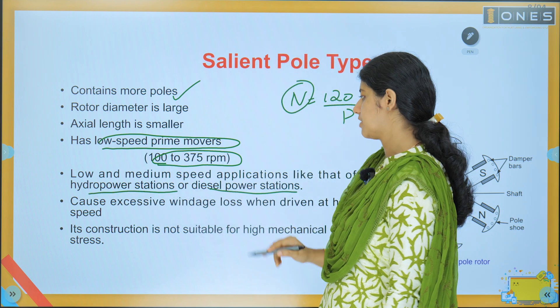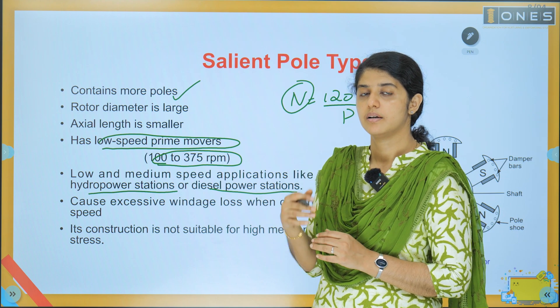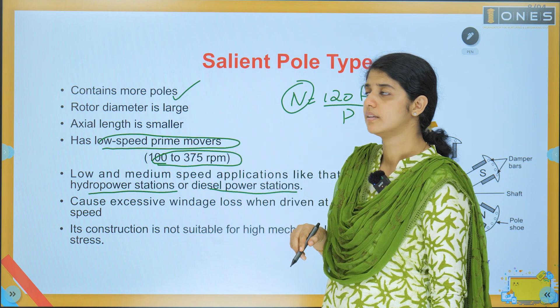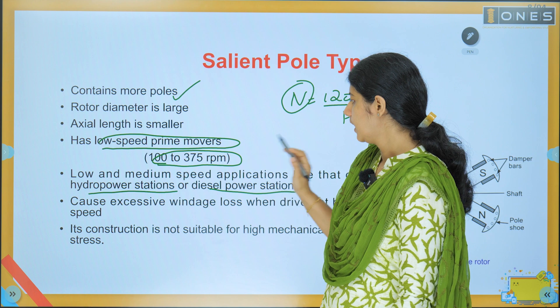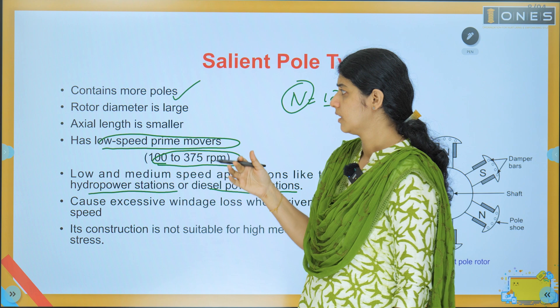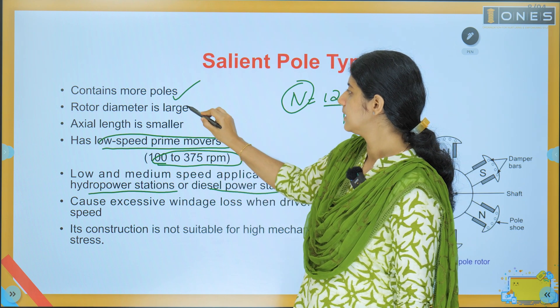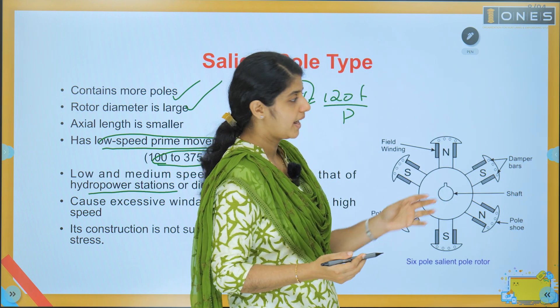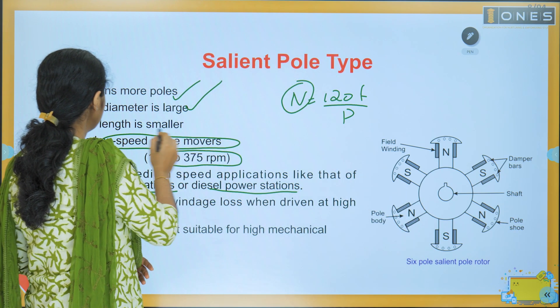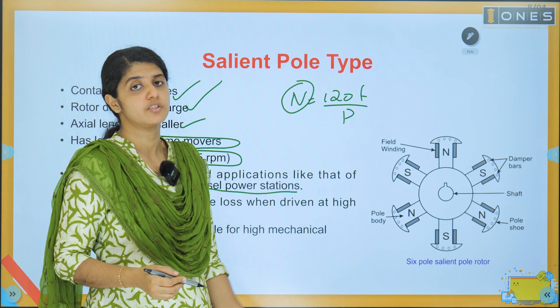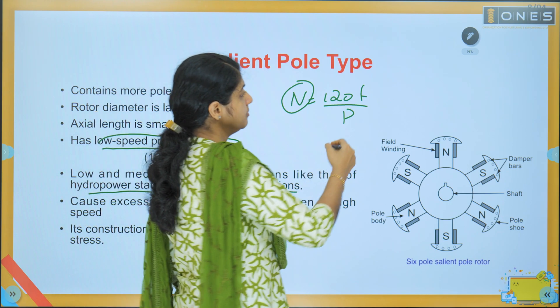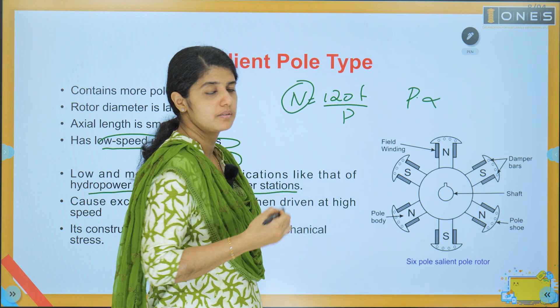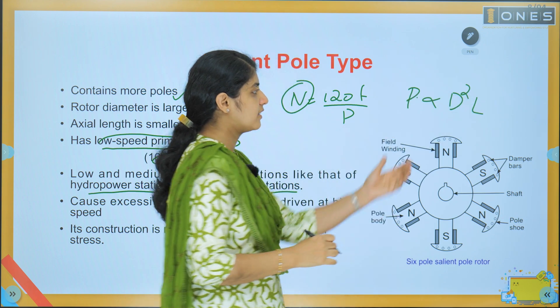We can use hydropower stations and diesel power stations. The speed range is 100 to 375 RPM, meaning the number of poles is more. The rotor diameter is large and the axial length is small. The output is proportional to the volume of the rotor: D² × L, where D is diameter and L is axial length. Since diameter is high, L is kept small.